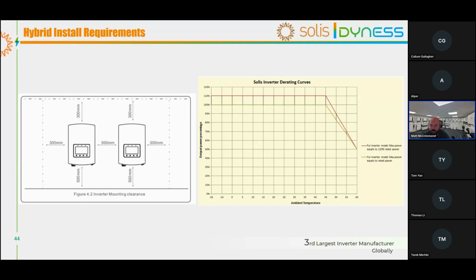In terms of installation and selection of where you place the inverter, something that's probably overlooked more than it should be by installers, and what I see a lot on social media and in a lot of pictures that are sent to me, is customers not taking into consideration the airflow around their inverter. Inverters work by derating based on temperature. If the temperature is higher, then the output is lower. We also have a caveat in our warranty that if you don't follow our instructions, it can lead to not being under warranty. So again, please consult the manual, understand what the limitations are, and then follow them.